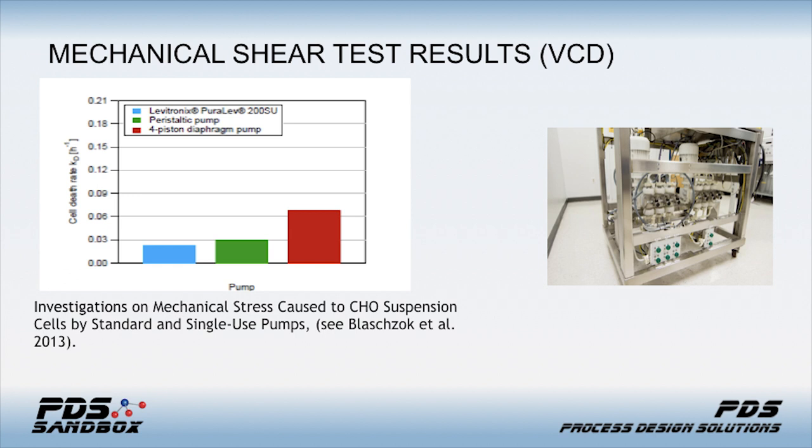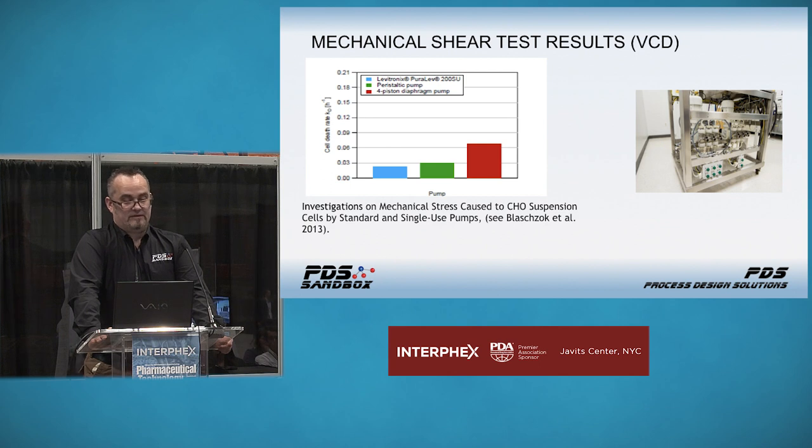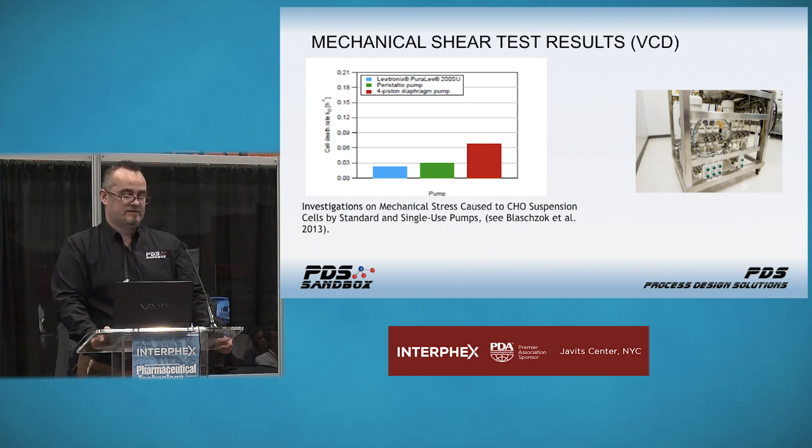We also ran viable cell density testing. Levitronix ran their own testing for viable cell densities, and their results support the Sauter mean diameter findings — what we witnessed in our testing was pretty close to theirs. We're roughly within five percent across the board between Levitronix and the peristaltic pump. The original testing was run with a Masterflex peristaltic pump; the testing we conducted shows an even tighter range compared to the Levitronix data. The Quattroflow data aligns with what we identified as well — a pretty sizable gap in terms of the amount of mechanical shear imparted.